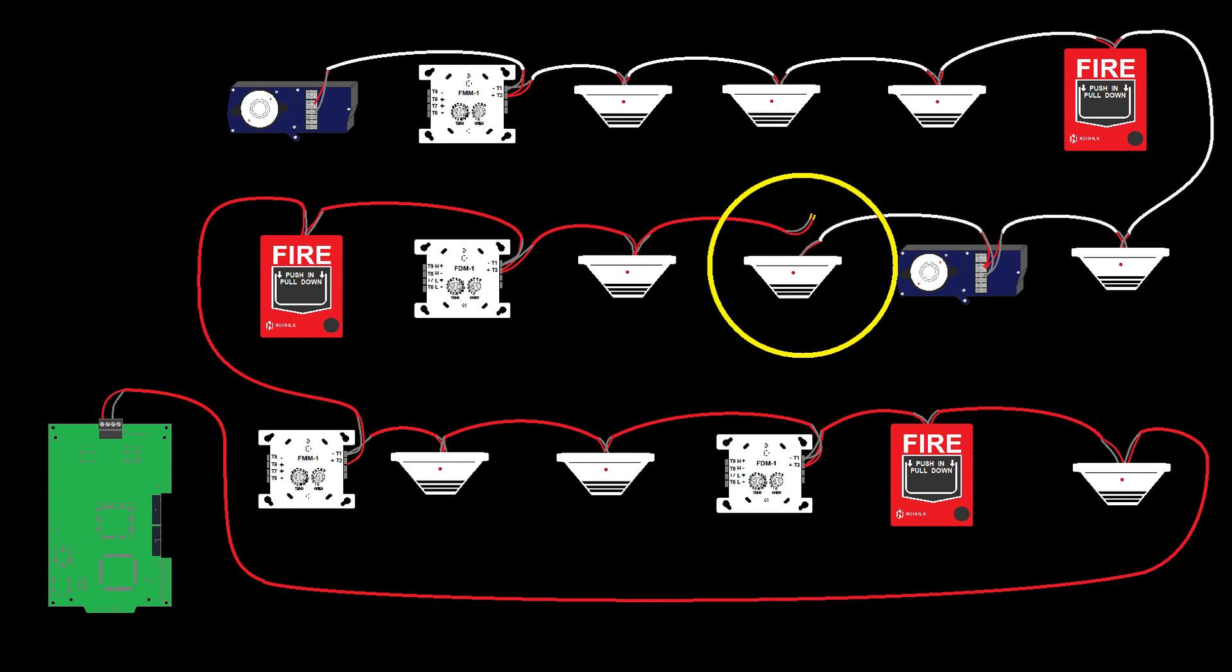Once we add this return leg back in to make the circuit a style 6 loop, that problem goes away. When a loop is configured for style 6, it sends its SLC communication signal out of both the B side and the A side of the card. So if there's an open circuit on any single wire, or even any pair of wires as we have here, all of the devices on the loop will still be able to communicate with the panel.